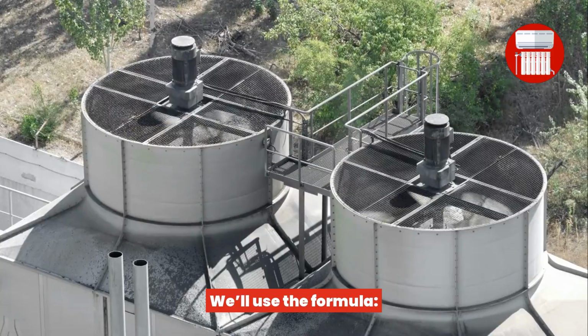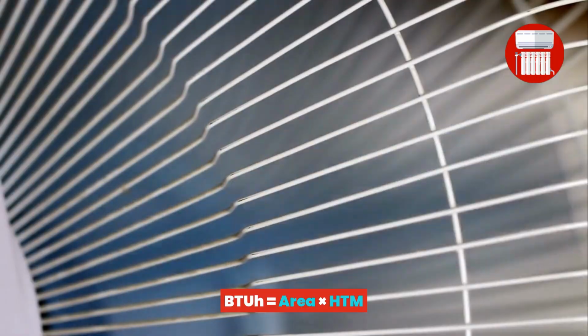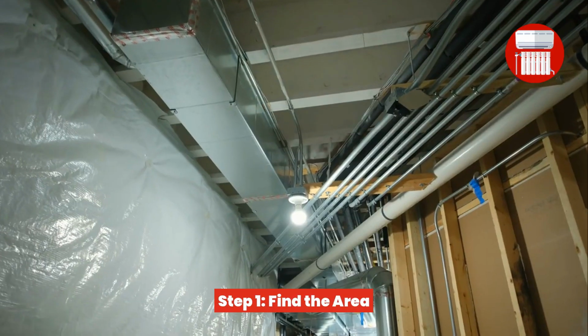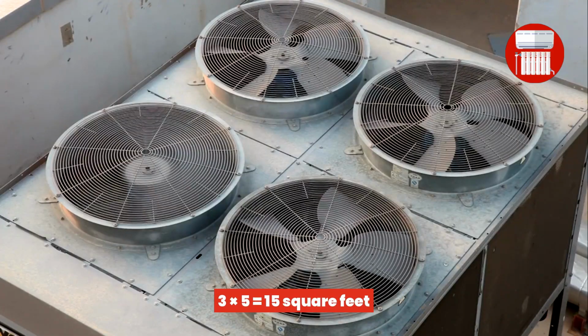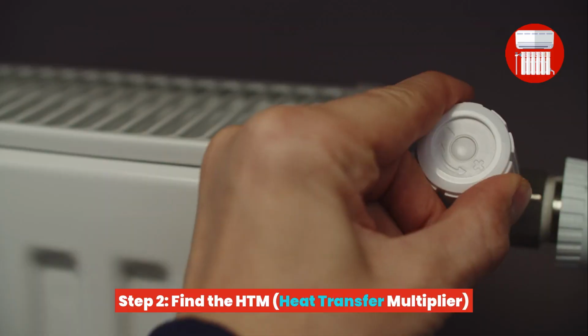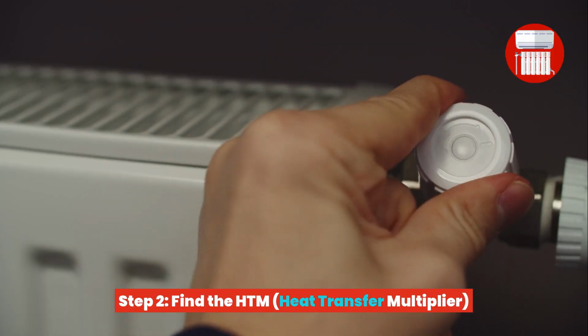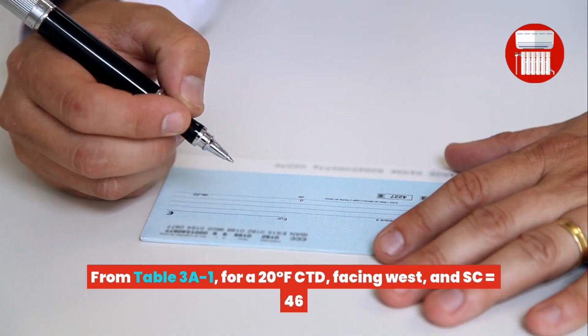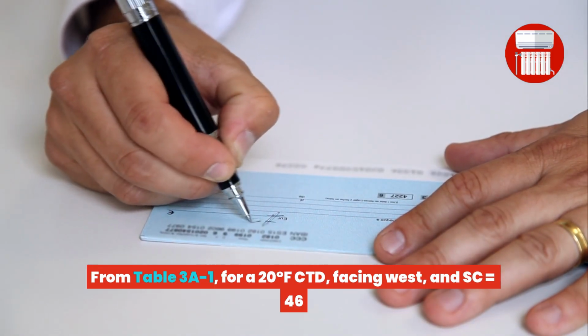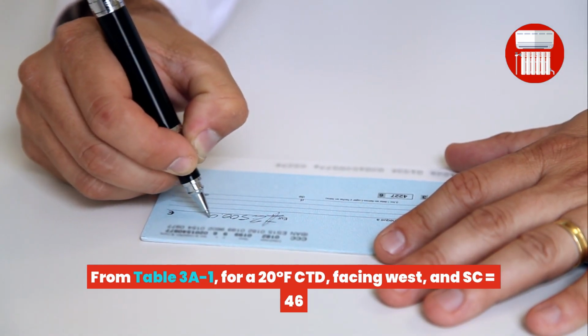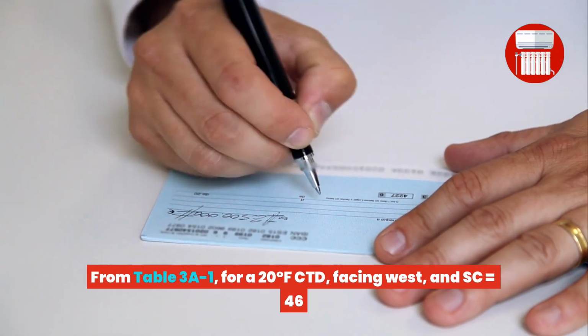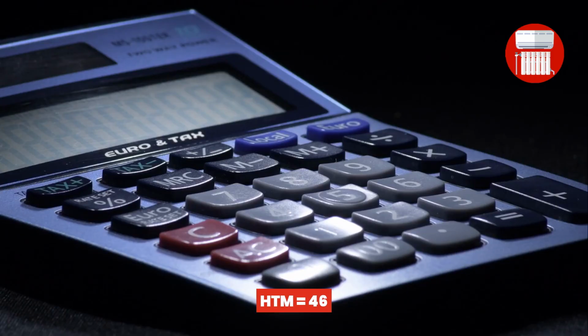We'll use the formula BTUH = area x HTM. Step 1. Find the area. 3x5 = 15 square feet. Step 2. Find the HTM, heat transfer multiplier. From Table 3A-1, for a 20 degrees Fahrenheit CTD facing west and SC = 0.46, HTM = 46.